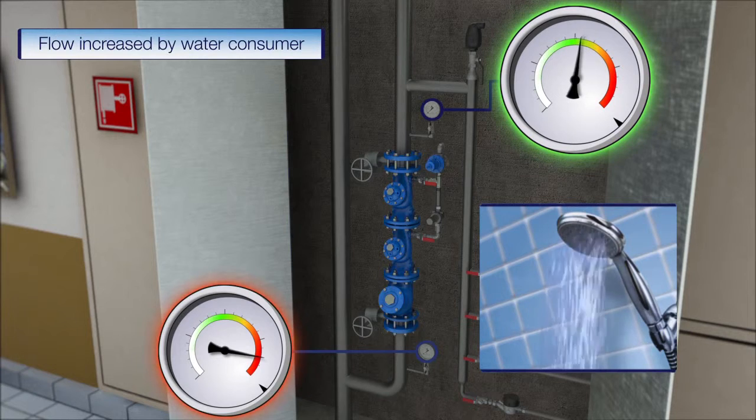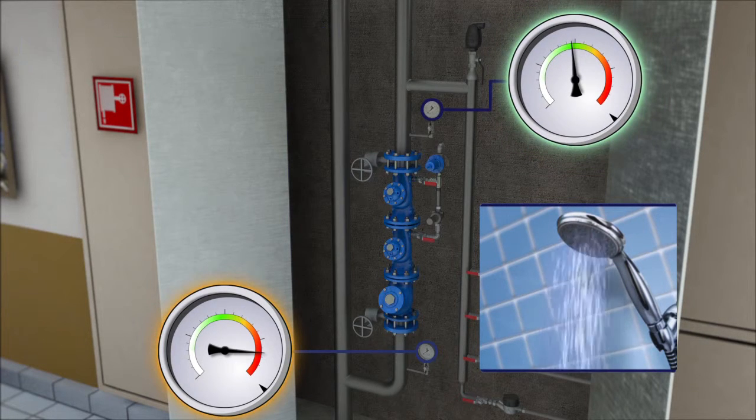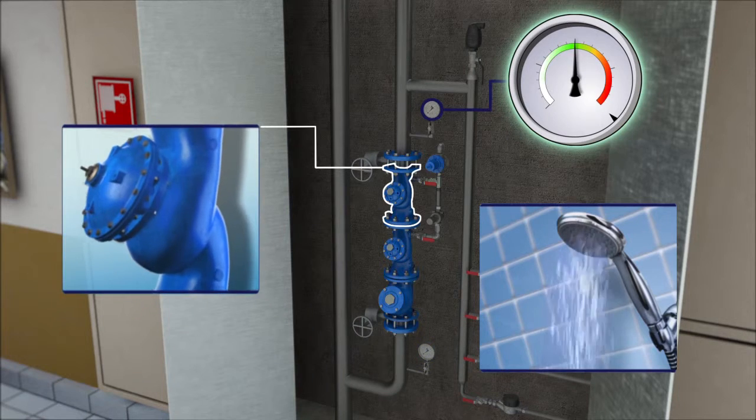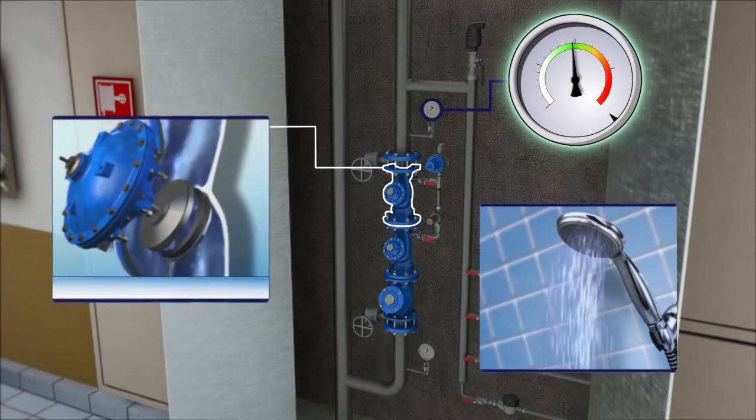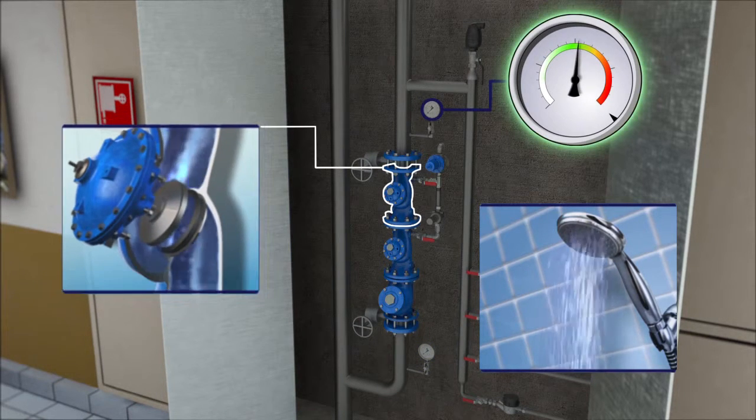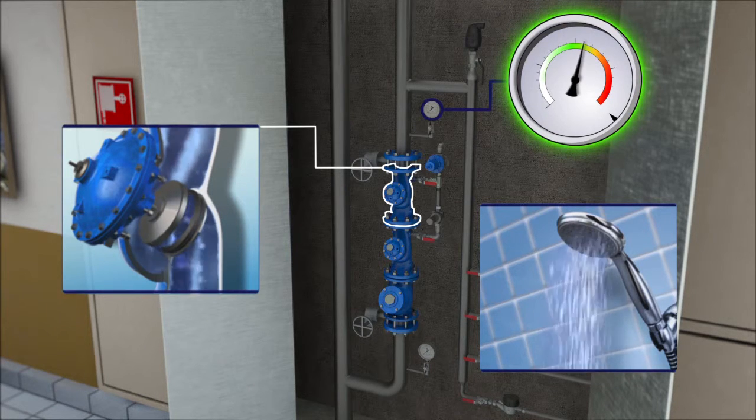When the residents start using water, the flow increases and the downstream pressure drops relative to the flow rate increase. The pressure reducing valve increases the pressure until the downstream pressure is back to normal level.